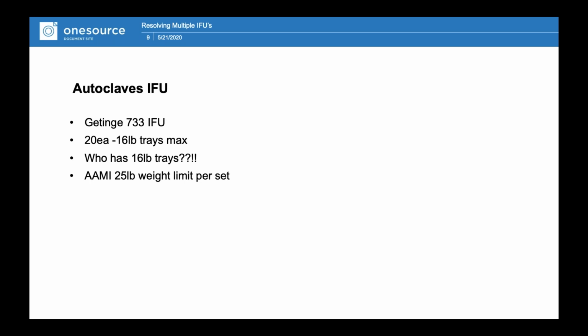It's scientifically known on the steam tables that for a vessel of this size, and this isn't an exact number, but for the sake of an easy visualization, let's say this vessel can create 1 liter. They know scientifically that 20 16-pound trays in that autoclave will generate 1 liter of liquid condensate. They know by their testing that the autoclave is also capable of re-evaporating that amount. So the lesson being, the minute we put that 1 extra tray on there, now we're generating 1 liter, 10 ounces, let's say, of condensate. The steam table isn't going to say, Dave, you're dealing with COVID, I know you're short-staffed, we're going to give you a break today. The autoclave doesn't care. It's only capable of re-evaporating that 1 liter of liquid condensate.